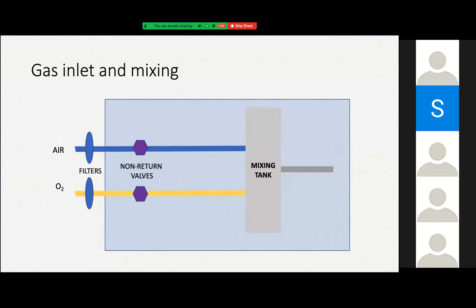Coming to the parts of the ventilator, the first part is the inputs: gas and power. The gas inlet — typically all ventilators have an air and oxygen port. Gases are filtered for any particulate material using air filters. To make flow unidirectional and prevent backflow, there are non-return valves. Flow, pressure, and volume are regulated by control valves.